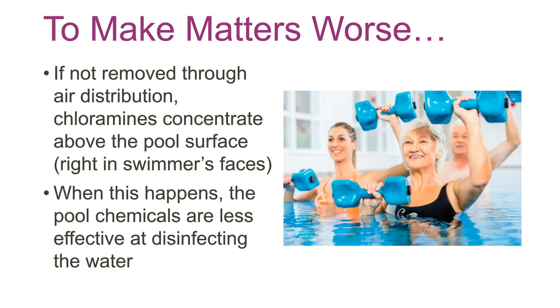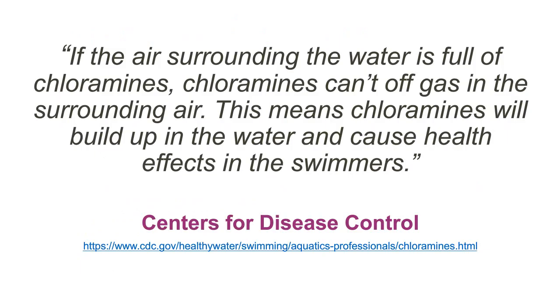And to make it even a little more challenging, if you don't get those chloramines away through good air distribution, they'll concentrate right above the pool surface, basically right where swimmers breathe. When that happens, pool chemicals are less effective at disinfecting the water. There's a reference there from the Center for Disease Control, basically making that statement that if the air surrounding the water is full of chloramines, it stops some of the process of off-gassing. They'll build up further in the water and cause more bad health effects for the swimmers.